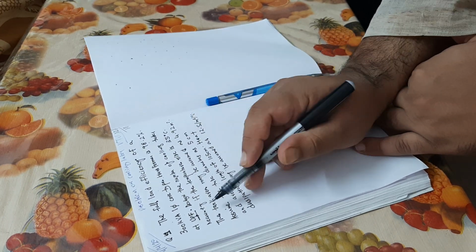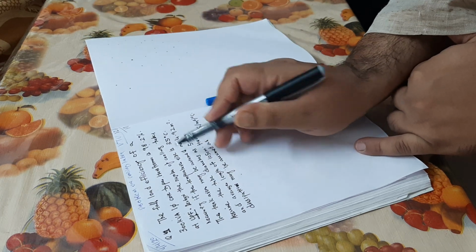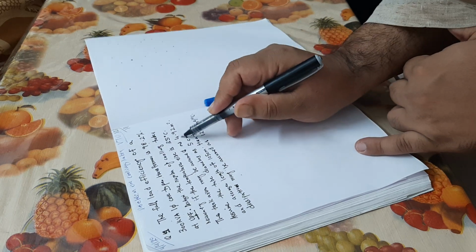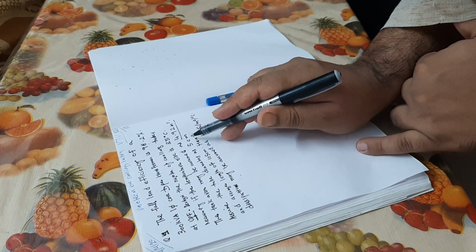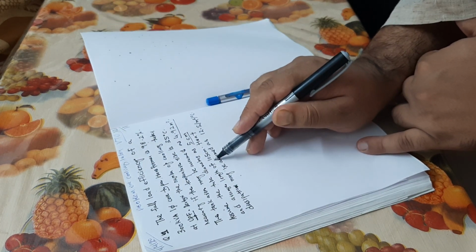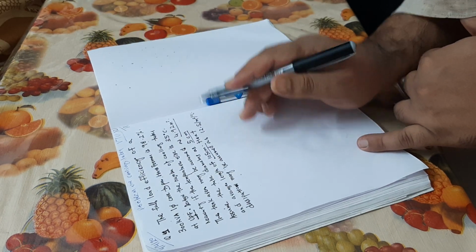Design the number of cooling tubes necessary if the temperature rise is 35 degrees Celsius. The tank area may be assumed as 4.92 meter square. Assume the tube diameter as 5 centimeter and average length of 105 centimeter. Heat dissipation may be assumed as 12.5 per meter square per degree Celsius.